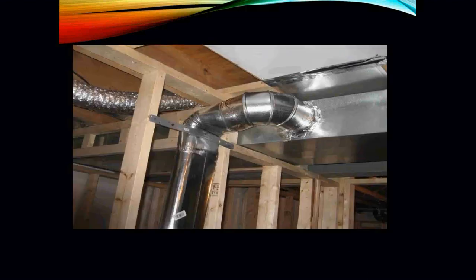Another example here: this guy is just using some foil tape for all of his joints. A couple of problems you can kind of see in this image - he has an adjustable elbow here, and he did not seal around these joints with any mastic or silver tape, so this area is a potential for a leak. He also did not mastic down his oval pipe here or use any silver tape along his seams, so that's also another area where you can have air leaks.